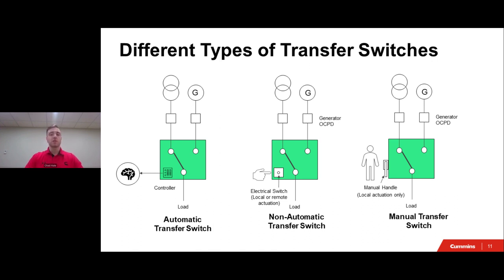Your transfer switch then detects that there is a power loss and will send a signal to the generator or your emergency power source to start up. Once the generator is ready to load, the automatic transfer switch will then initiate the transfer to the backup source. Once again, that backup source being that generator.